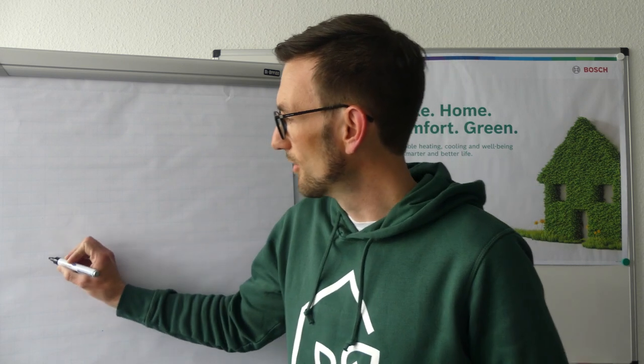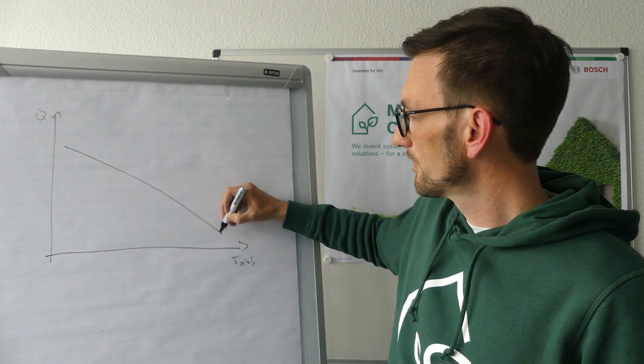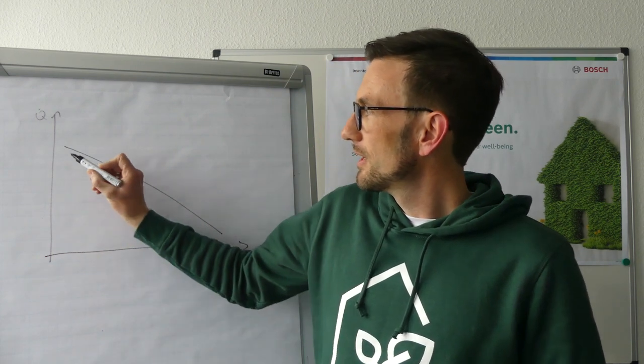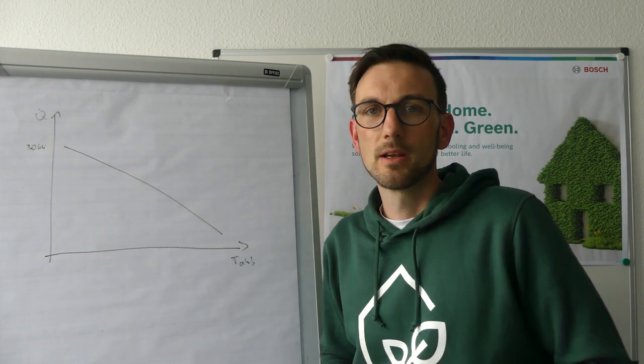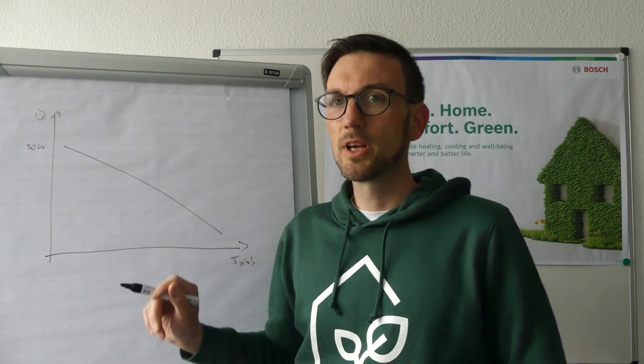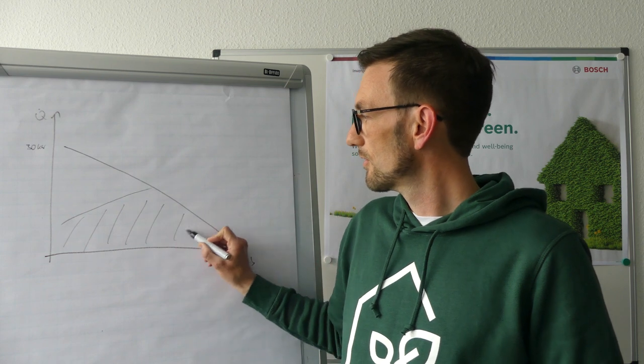To show you the benefits of a hybrid I would like to draw a picture. Over the outdoor temperature, the heat demand of your building looks like this — this is a simplified sketch just to make the point clear. If we have a building with a fairly high heat demand and a request for high flow temperatures, let's take 30 kilowatt as an example, you need a very large heat pump to provide this heat. The benefit of a hybrid is that you can use a much smaller heat pump — roughly 30% — and this heat pump will heat your house very efficiently.